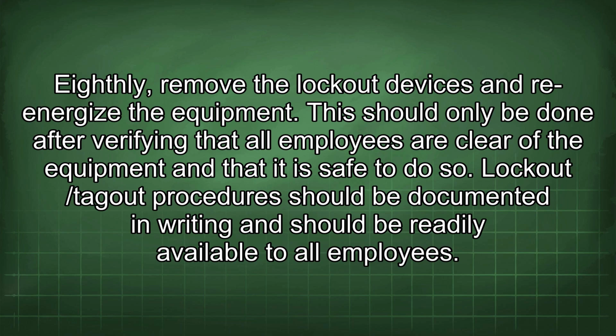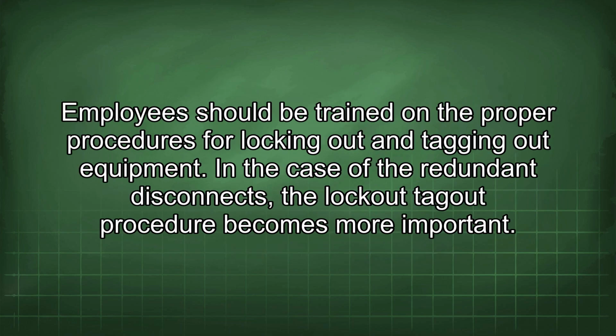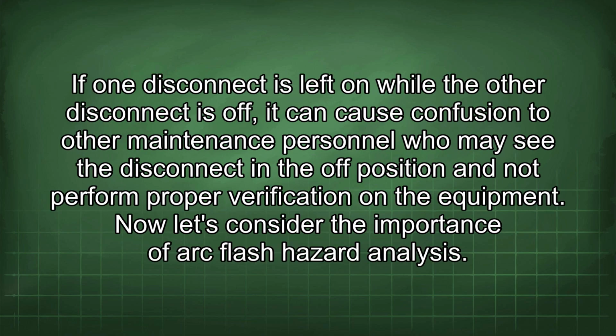Lockout/tagout procedures should be documented in writing and should be readily available to all employees. Employees should be trained on the proper procedures for locking out and tagging out equipment. In the case of the redundant disconnects, the lockout/tagout procedure becomes more important. If one disconnect is left on while the other disconnect is off, it can cause confusion to other maintenance personnel who may see the disconnect in the off position and not perform proper verification on the equipment.